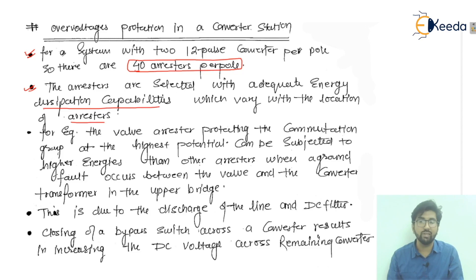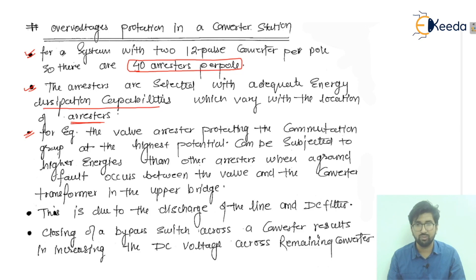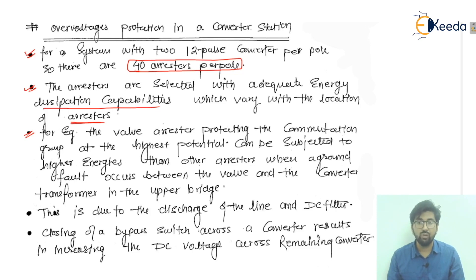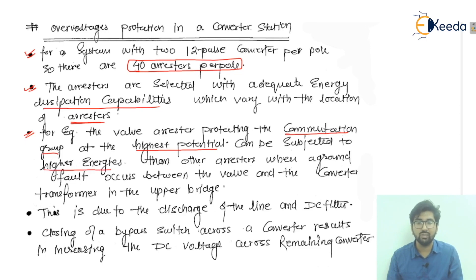The energy dissipation capability varies with the location of the arrestors. For example, the valve arrestor protecting the commutation group — we have two types of commutation groups: the positive commutation group numbered 1, 3, 5 and the negative commutation group numbered 4, 6, 2. The valve arrestors protecting the commutation group at the highest potential can be subjected to higher energies than other arrestors.